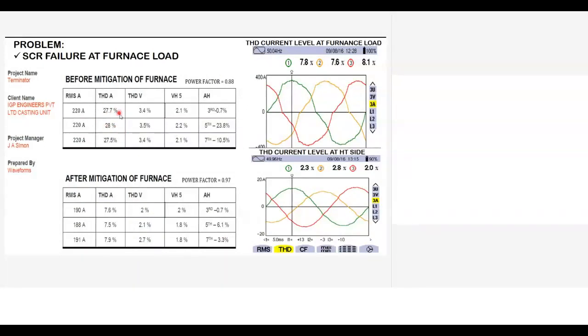The current harmonics was 27.7, the voltage harmonics was 3.4, and the fifth harmonic was almost 23%, and the seventh harmonic was, you can see the variation also in the harmonic levels. So this is the problem. And then after we installed this, we found that the current harmonics came down to 7.6, 7.5, 7.9, which is within the IEEE limit, much below the IEEE limit.